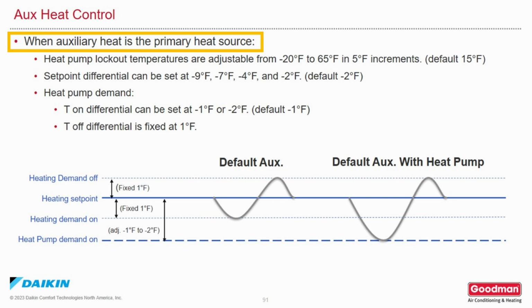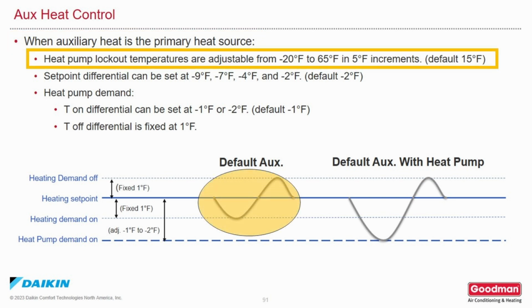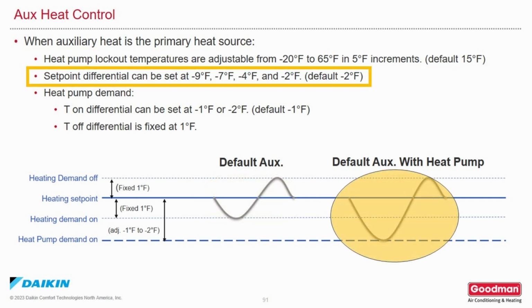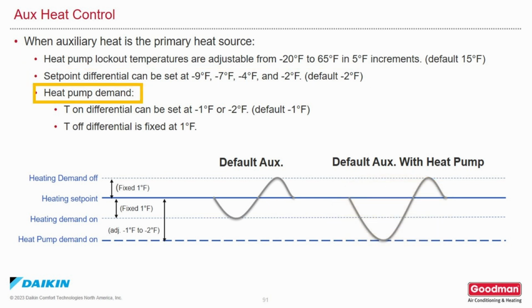When auxiliary heat is your primary heat source, the heat pump lockout temperatures are adjustable from minus 20 to 65 degrees Fahrenheit in 5-degree increments. Default is 15 degrees. Set point differential can be set at minus 9, minus 7, minus 4, and minus 2 degrees Fahrenheit. Default is minus 2. Heat pump demand T-on differential can be set at minus 1 or minus 2 degrees Fahrenheit. Default is minus 1. T-off differential is fixed at 1 degree Fahrenheit.